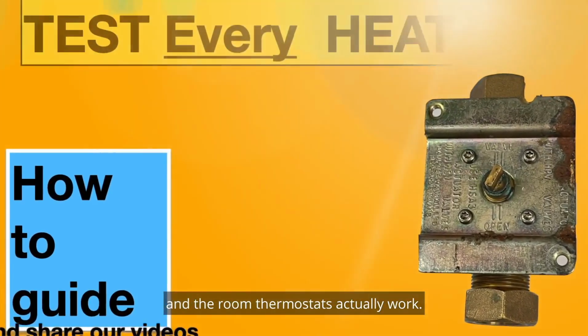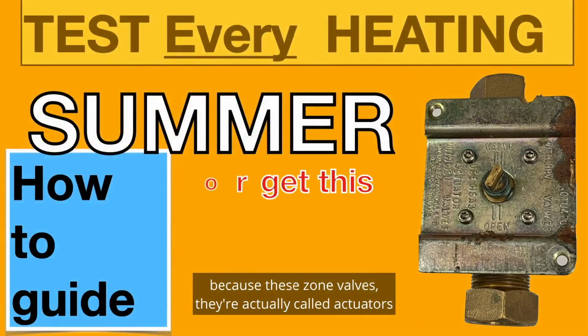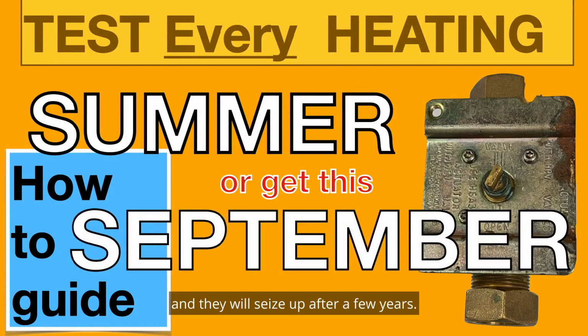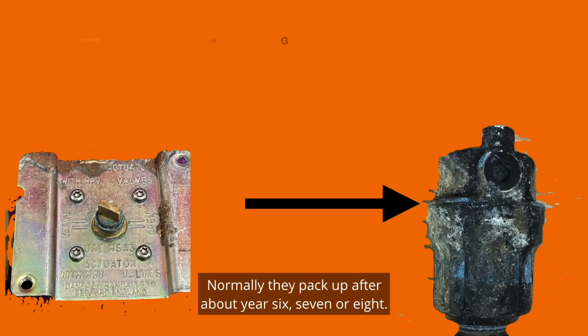This is just to remind homeowners, installers, breakdown engineers, everyone who has central heating to check that the valves actually work and the room thermostats actually work and the programmers. And as we can see here, it's absolutely vital because these zone valves, they're actually called actuators, and they will seize up after a few years. Normally they pack up after about year 6, 7 or 8.